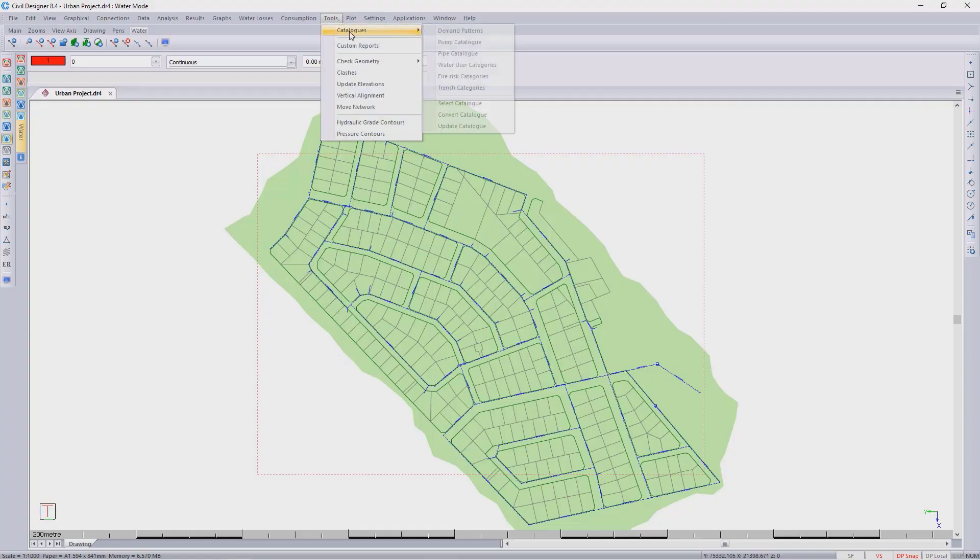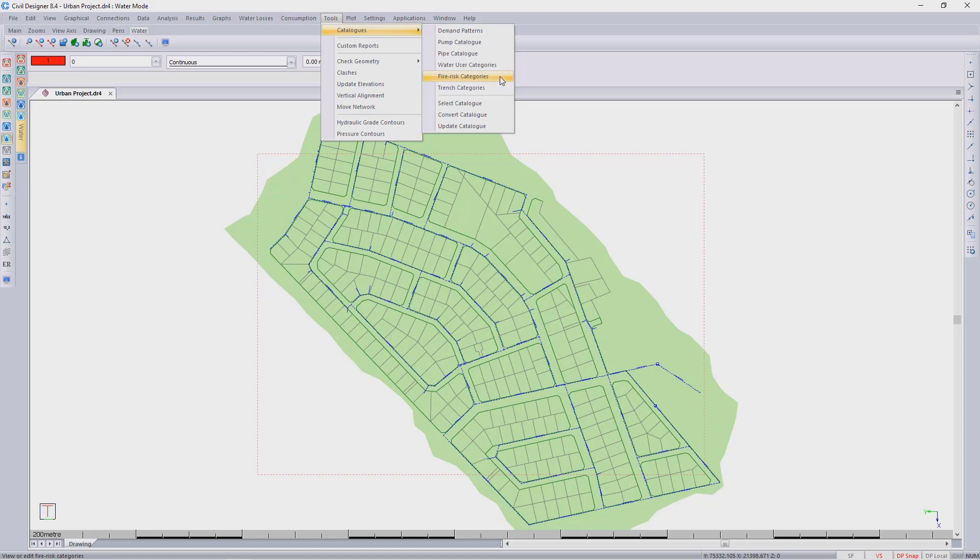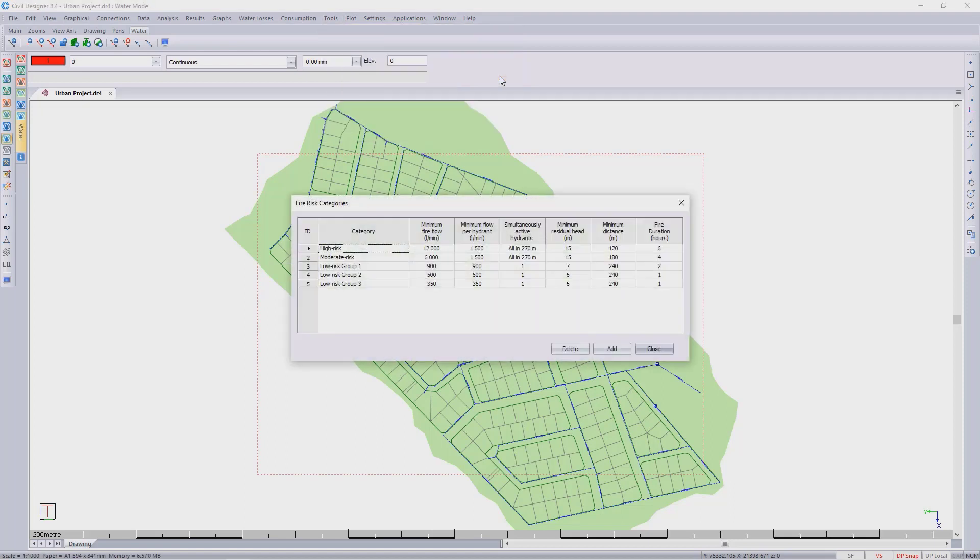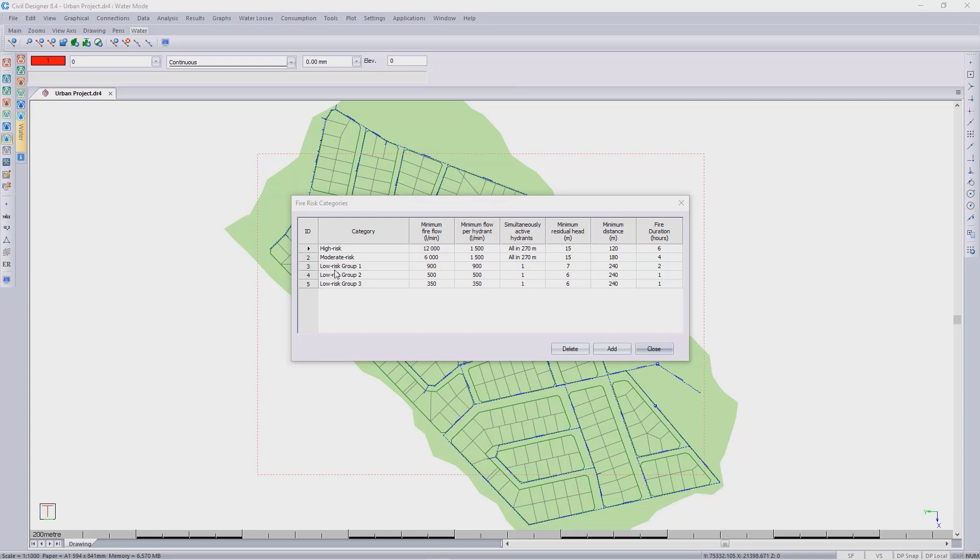Our categories for the fire hydrants will be under Tools, Catalogs, Fire Risk Categories. Here you can see we've shipped the software with five categories. We have the high risk, for example, that requires a minimum fire flow of 12,000 liters per minute. We also have the minimum flow per hydrant during an event of 1,500 liters per minute.